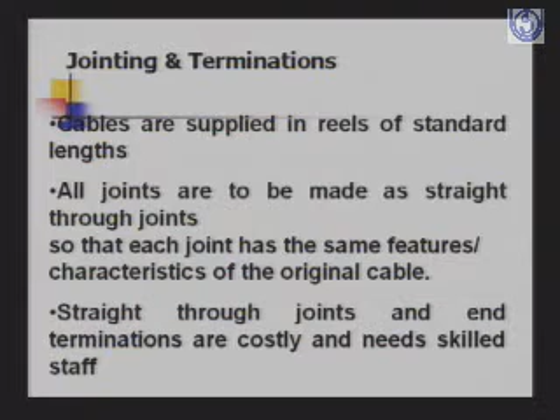Then the jointings and terminations for the cables are very important because the cables are supplied in reels of standard lengths. And you have to make joints to get the desired length of the cable, and the joints are to be made as straight through joints so that each joint has the same features or characteristics of the original cable. The straight through joints and end terminations are costly and they need skilled staff. That is why, as I said, the cable is a costly affair.